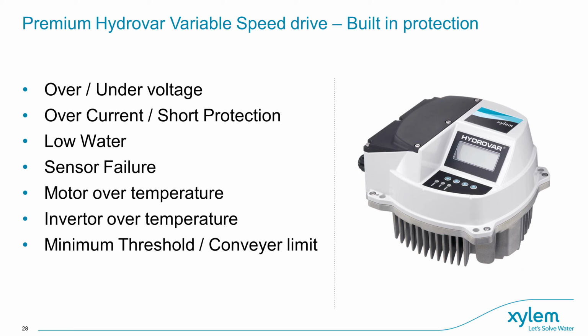The Hydrovar has built-in electrical protection, which includes over and under voltage, over current, and motor over temperature. Built-in dry run protection for either a float switch in the break tank or a pressure switch on the suction. It also monitors the status of the pressure transducer and monitors the temperature of the drive itself. It stops the set in the event of a burst pipe, reducing the impact of flooding within the plant room.